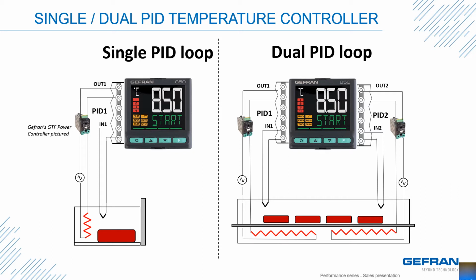The Performance series could be a two-loop PID controller. What else could I do with that? Possibly we could link the PIDs or have the set points change via logic or math. Maybe track the actual temperature on one side and use that as a set point on the other, keeping both sides heating together at the same rates.